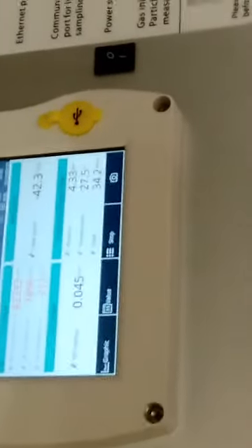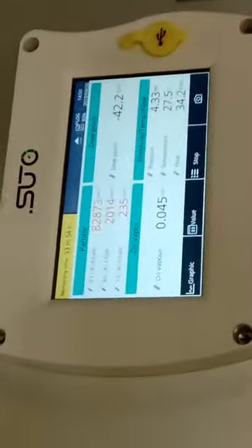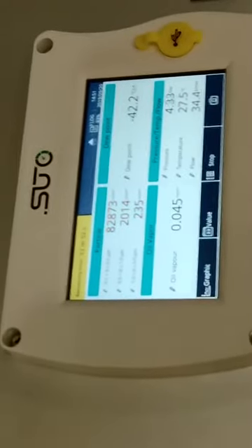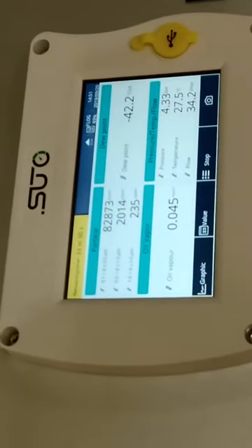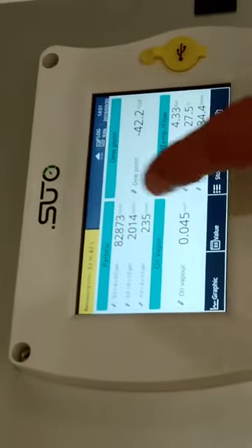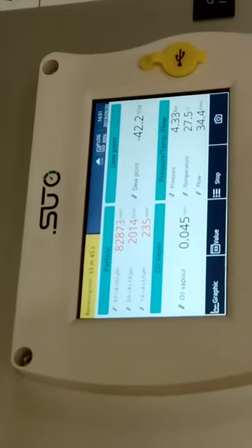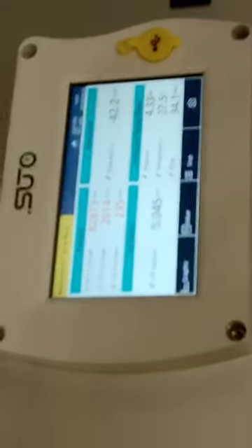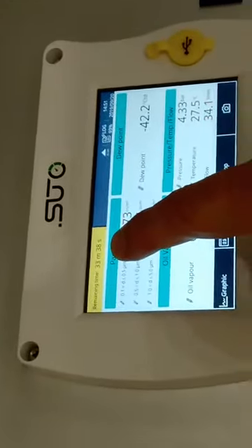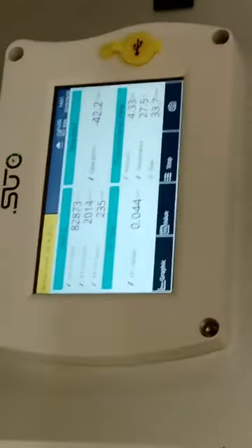So for 1 hour you do the reading. It depends a bit on the class you select. If you want to go to the highest class, +1, I recommend you measure for 1 hour at least. The particles will be updated only once a minute, so it will be stable for 1 minute and then refresh. And this is the program time, so we have 33 minutes left.